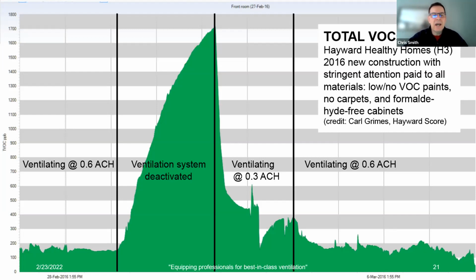And what we're basically looking at, the faint gray vertical lines are each demarking a day. At the beginning of the week, we see 2 days where we're operating at a fairly consistent ventilation rate. And that ventilation rate was 0.6 air changes per hour. So basically 2/3 of the entire building volume of air was being exchanged every hour. They did an experiment and shut off the ventilation system for about 2 days. And over the course of those 2 days, you can see the VOC concentration spiking up north of 1,700 parts per billion.